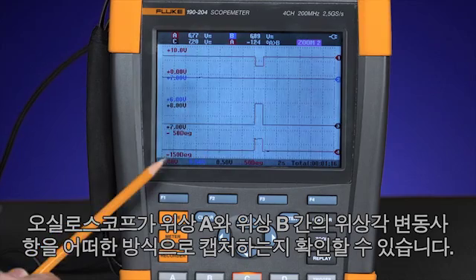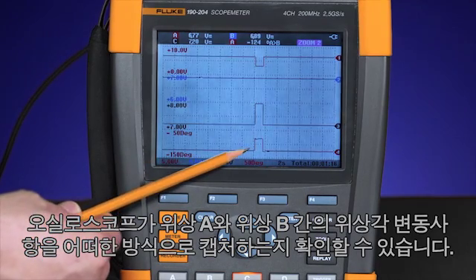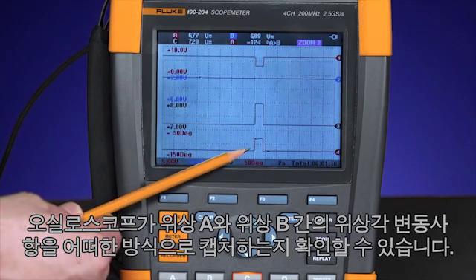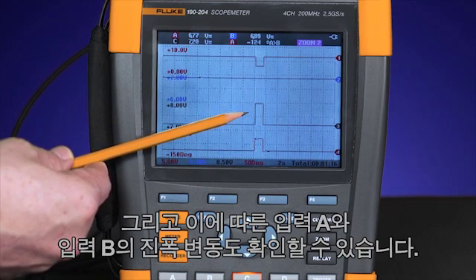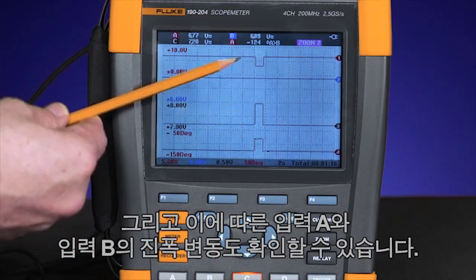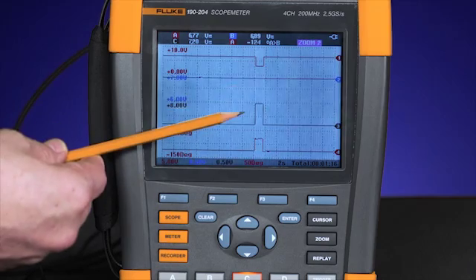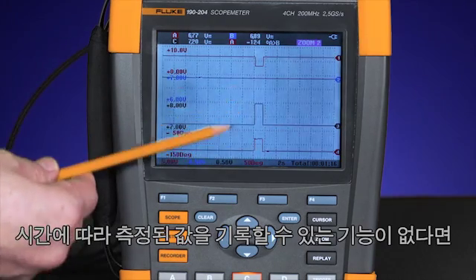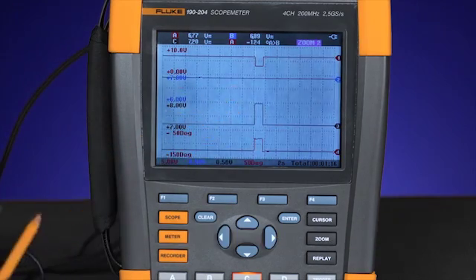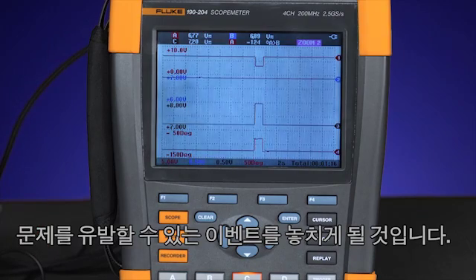Here you can see how the oscilloscope has captured a phase angle change between phase A and B, and you can see the corresponding change in the amplitudes of input A and B. Without the ability to record those measured values over time, you would most likely miss the event that could be causing your problems.